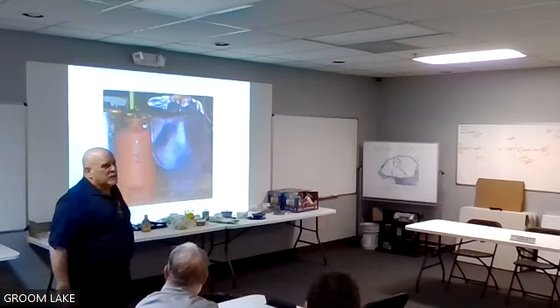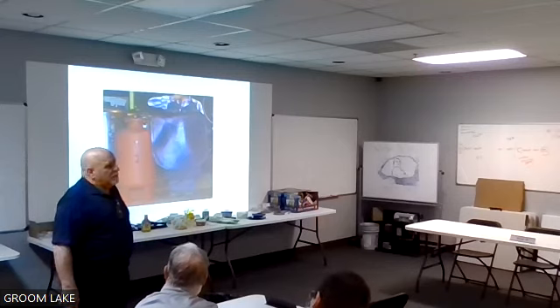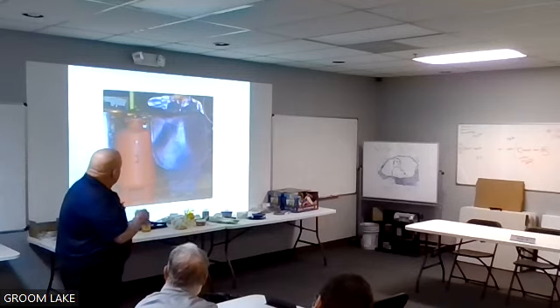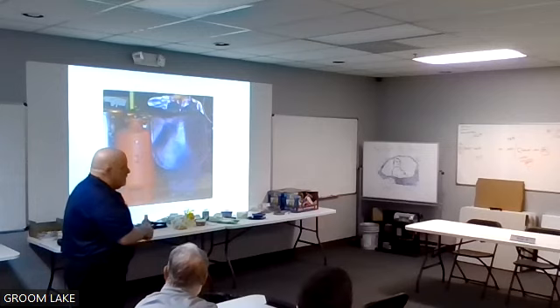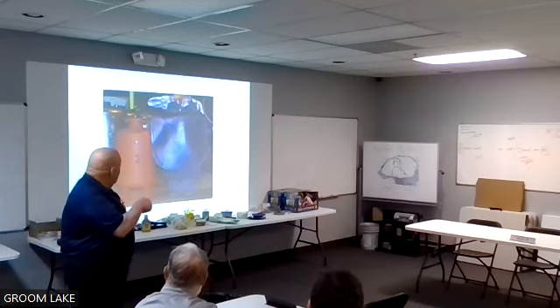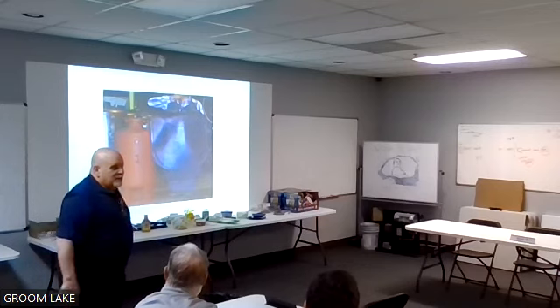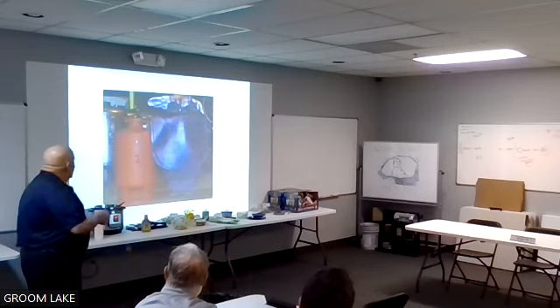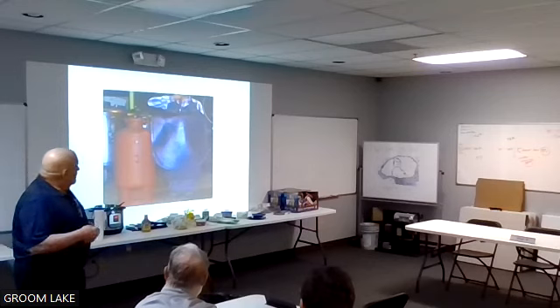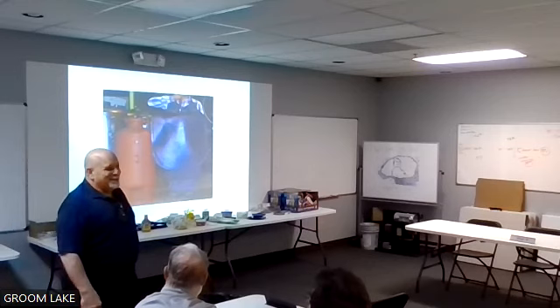So that's why they use nitrogen. But then it's a dry layout, you know, no moisture, no oil, no nothing. But you can see that bladder will go into that tank. Like I said, the diaphragm and these, you can pull this bladder out and replace it. The only problem is, let's say this is a $3,000 tank. That bladder is about $2,200 of it.